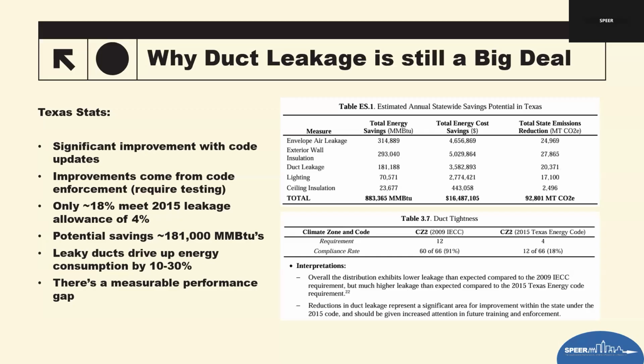So when you put all this together, you see a clear performance gap. It has been getting better over time. We still have a lot of cities on the 2015, some on the 18, some on the 12, some on the 21. It's a mixture of all, but we still see issues even on the newest code cycles being adopted. We still see issues with duct leakage. The technology's there to actually prove that we can get those things done, but on-the-ground performance still is consistently not meeting targets. So that's why the 2024 IECC changes, especially the new leakage tables and clearer testing requirements, are so important.